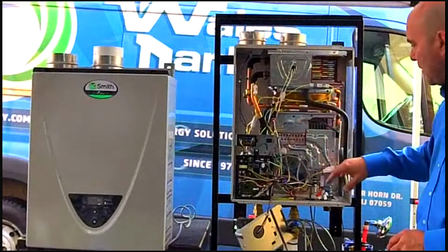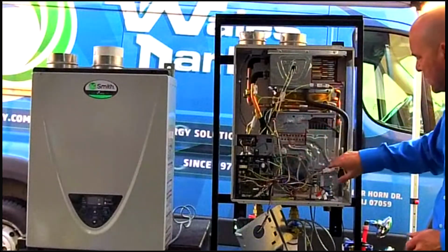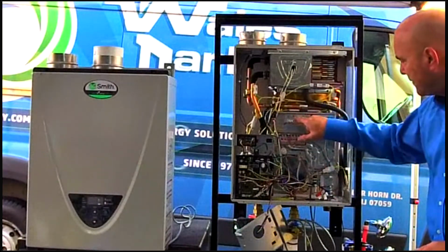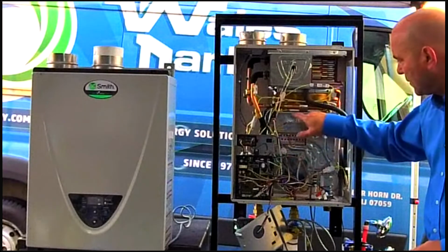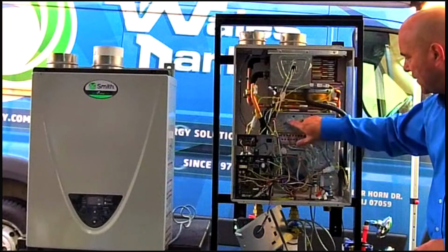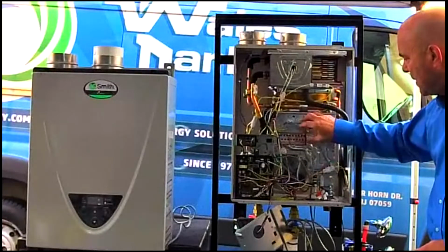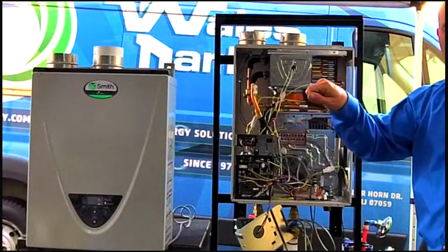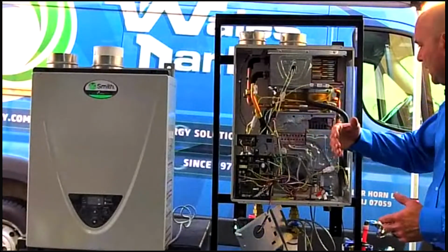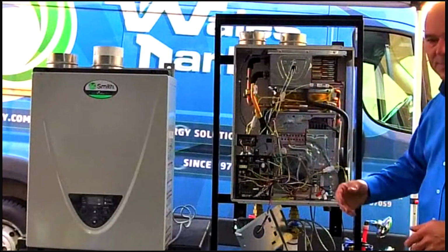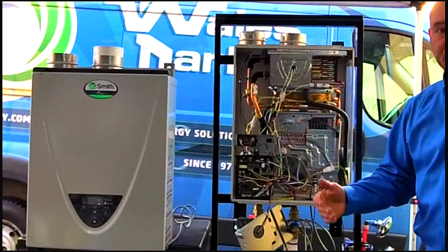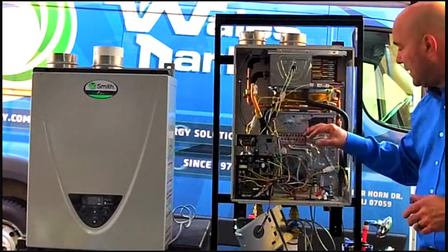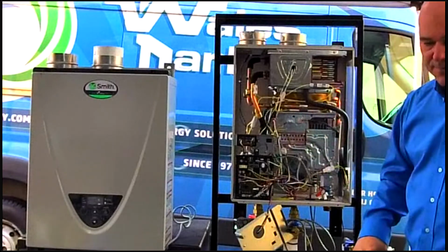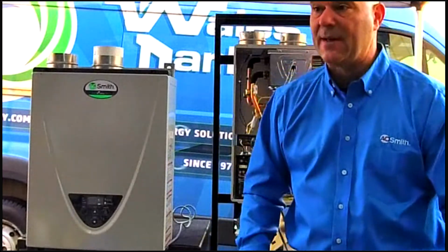If you need to pull the burner tray, you'll take those same screws out, and then there's a few more screws along here. You'll remove this cover plate for your igniter and your flame rod, and then your whole burner tray will slip out, and then that can be cleaned. And then you can inspect the bottom side of the primary heat exchanger if needed. You will need a gasket kit for that. So if you're going to make those changes, just be prepared to have a gasket kit.